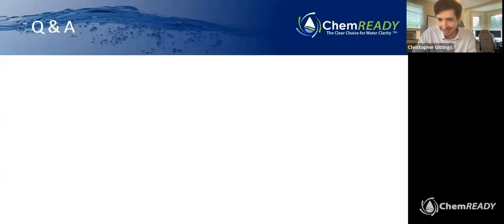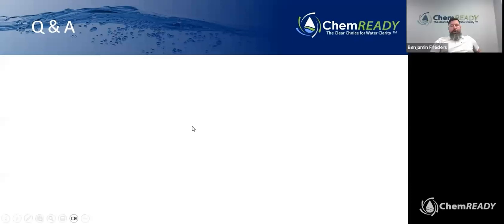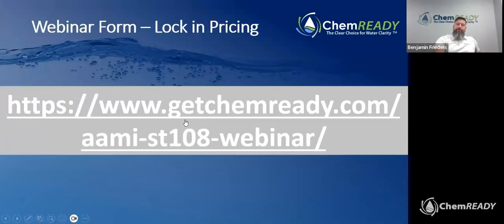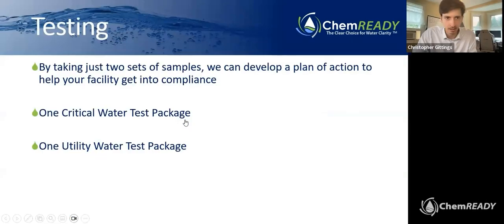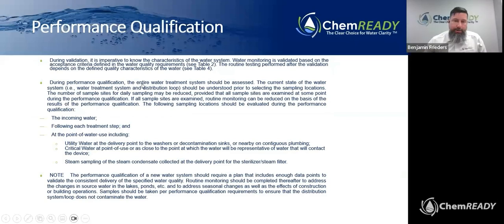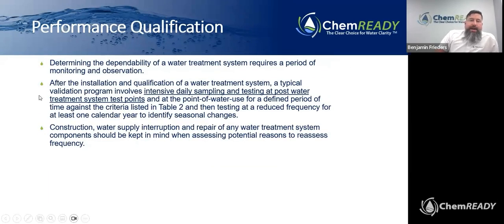Oh, here we go. Lynn asks, can you speak to the recommended versus required? There seem to be several recommendations. Sure. And just to clarify, we're talking the compliance testing itself, I assume. You can correct me if I'm wrong. I'm guessing so. Yeah, she says yes. Okay. So the requirements for the performance qualification, as I mentioned before, to be 100% compliant, it says, going back to here, a typical validation program involves intensive daily sampling and testing at post-water treatment system test points and at point of water use for a defined period of time against the criteria listed in Table 2, and then testing at a reduced frequency for at least 1 calendar year to identify seasonal changes. So, as you might notice, it is very ambiguous and it is not hard and fast.